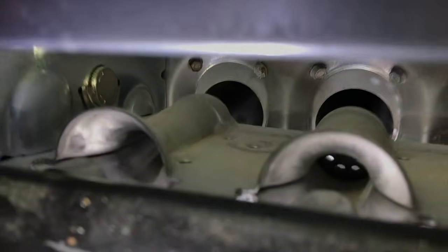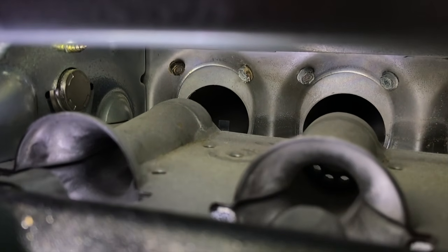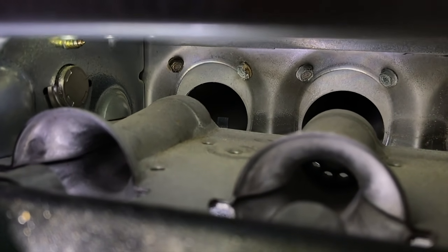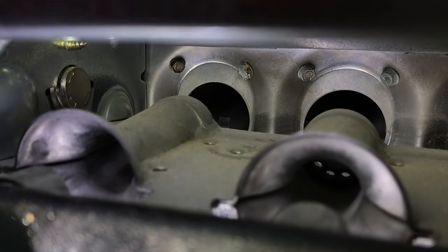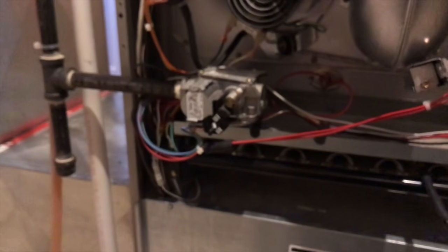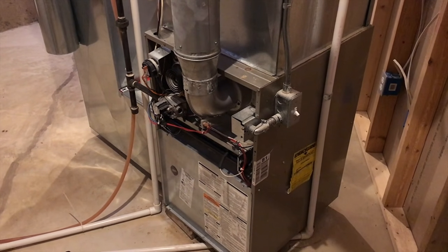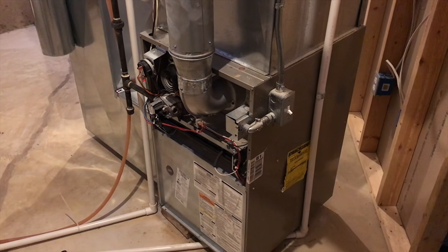And over time, your igniter fails, and in the event that your igniter fails, guess what? It will never ignite your furnace, thus never actually igniting your burners, and you will never get heat out of your furnace. So with that said, those are the 3 most common causes that will lead to your furnace blowing cold air out of your vents. Hopefully one of these 3 common causes can get your furnace back up and running properly.